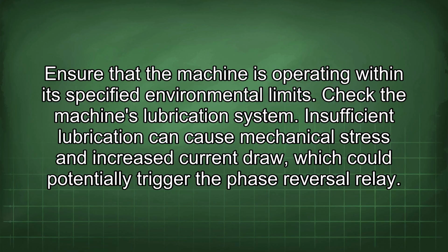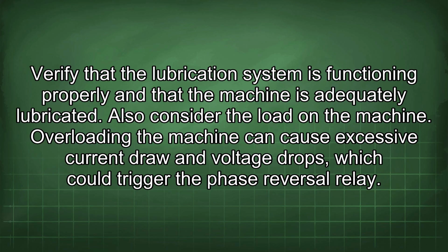Check the machine's lubrication system. Insufficient lubrication can cause mechanical stress and increase current draw, which could potentially trigger the phase reversal relay. Verify that the lubrication system is functioning properly and that the machine is adequately lubricated.